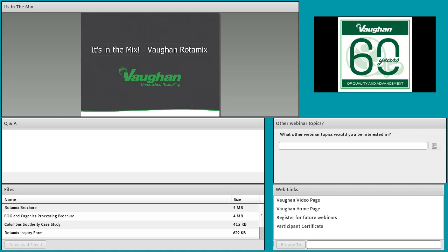And, that's a great question. So lime stabilization, generally, you may be able to get away with a Triton pump. It just depends on how sure you are that what you have in that tank is just lime. So if you're potentially going to have other contamination where you might go past the ball pass for the Triton pump that you're looking at, or may cause issues for the nozzles, we may suggest a chopper pump, but definitely potentially a Triton screw pump could be the best fit for a lime stabilization application. We would just need it depends, but yes, it's potential.